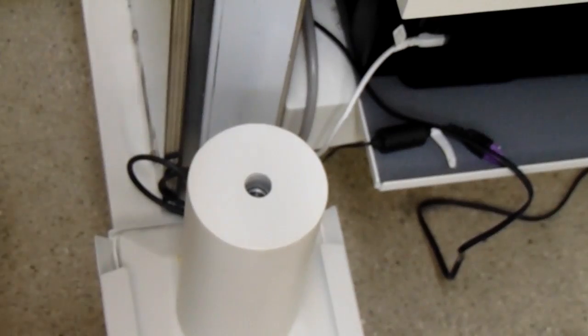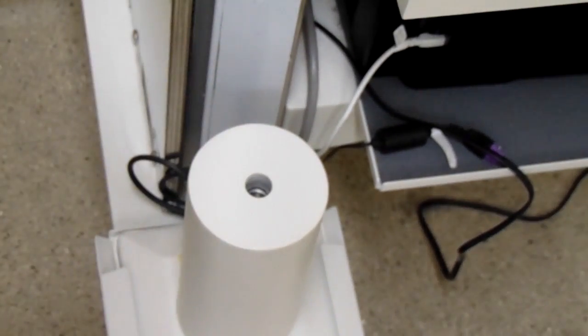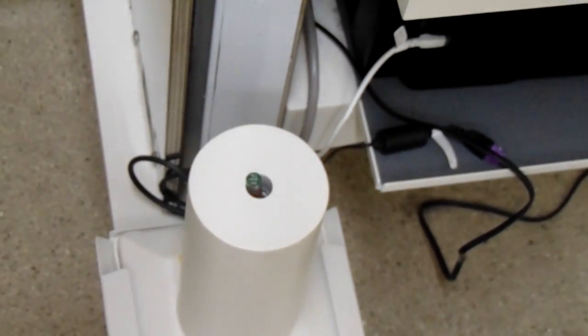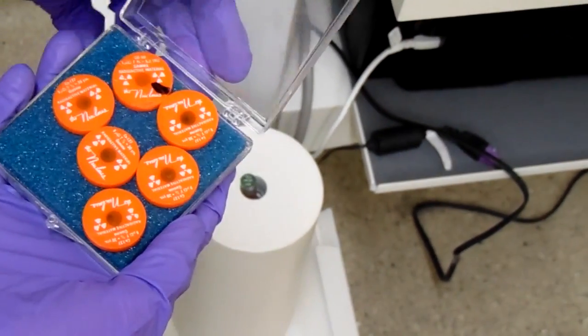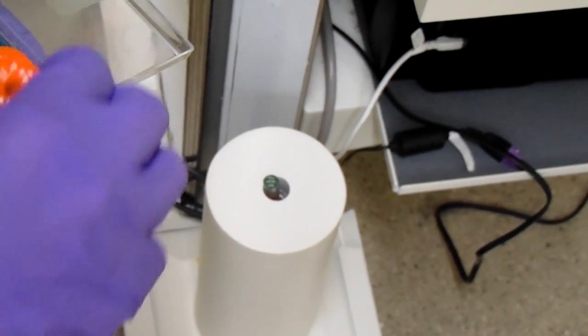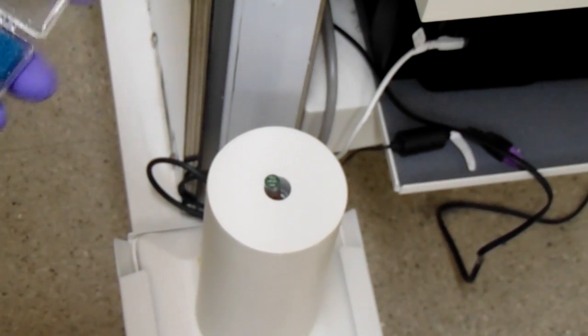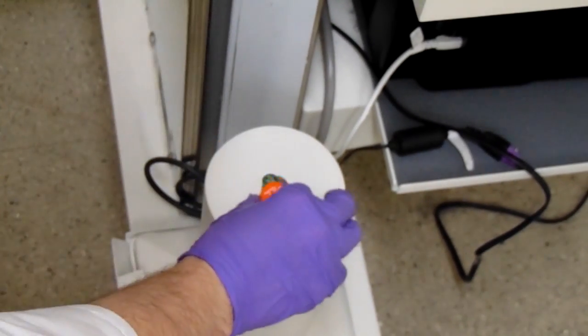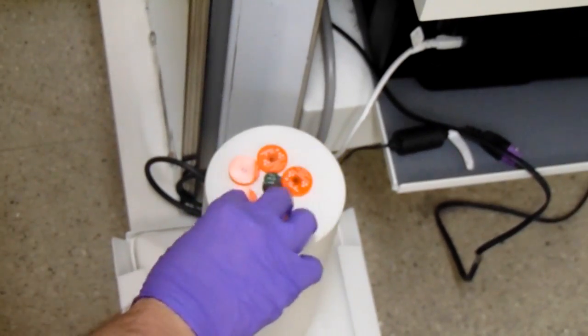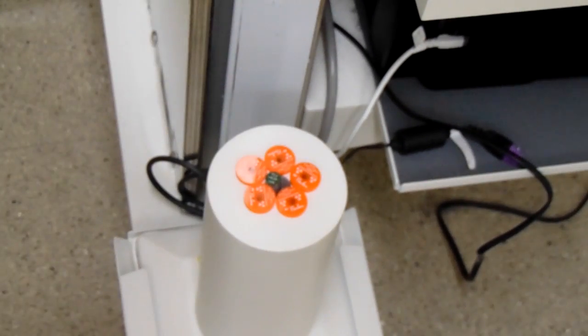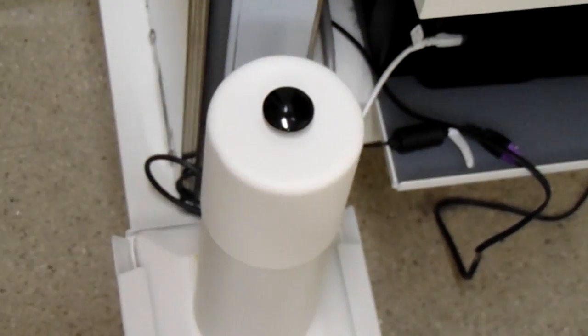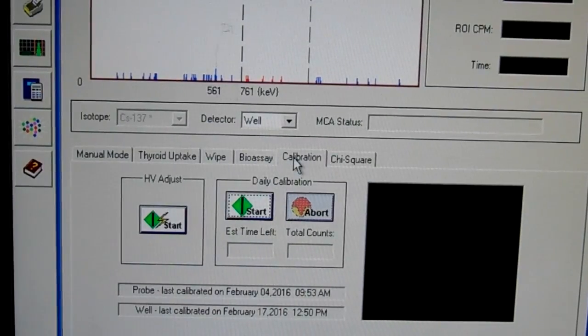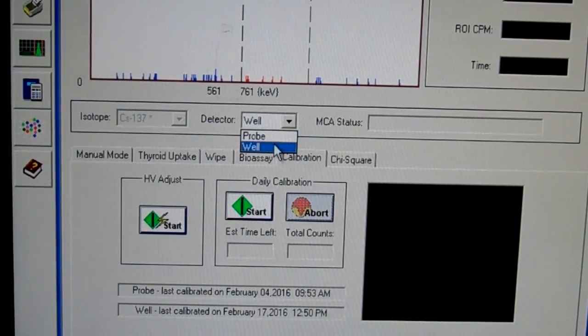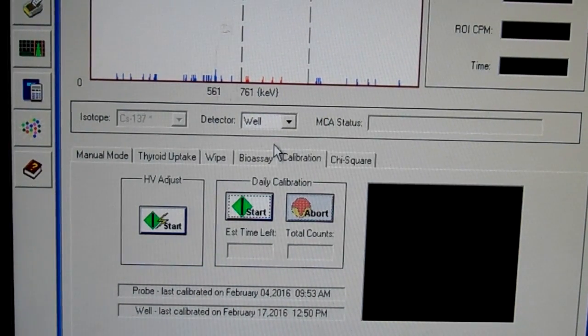So what you're going to do is put the bar source into the well of the well counter, and then you're going to take your disc sources and place them around the bar source. You can stack them all at once, but I just like to put them in a circle around it so that you're not closing the lid right on top of the disc. Now, onto the software, you're going to go to calibration and click the drop-down menu and go to well, and then you're going to hit start and the computer will start doing its counts.